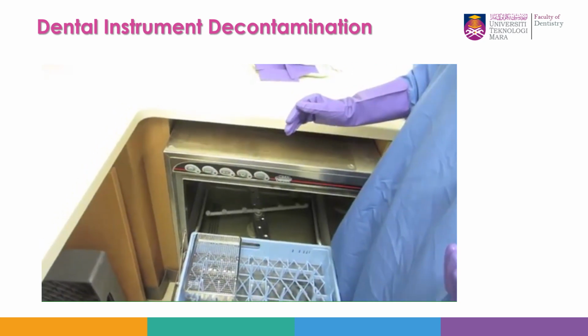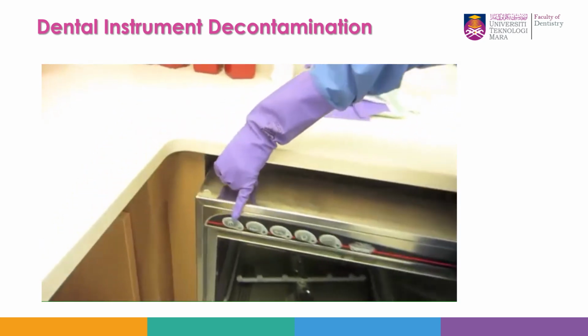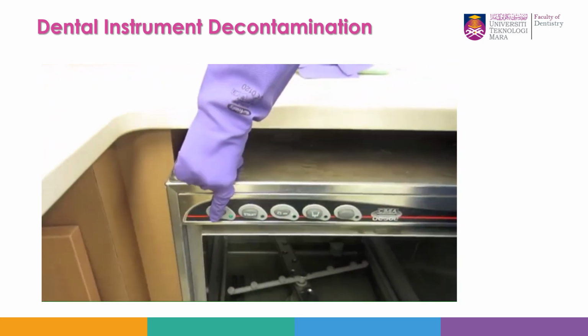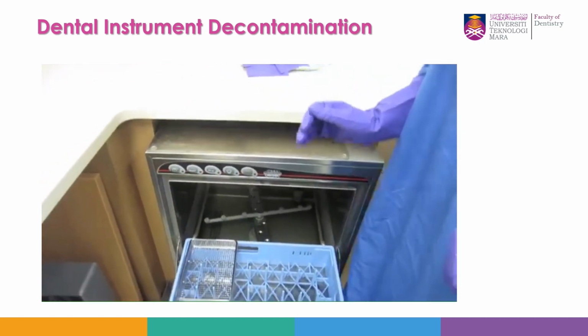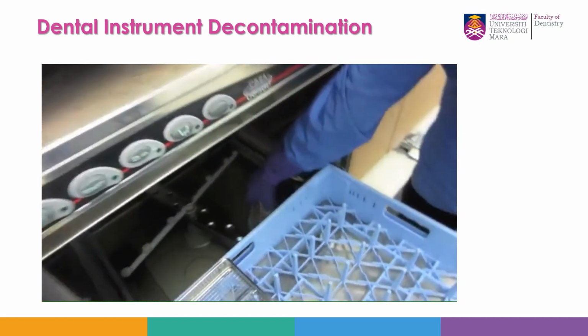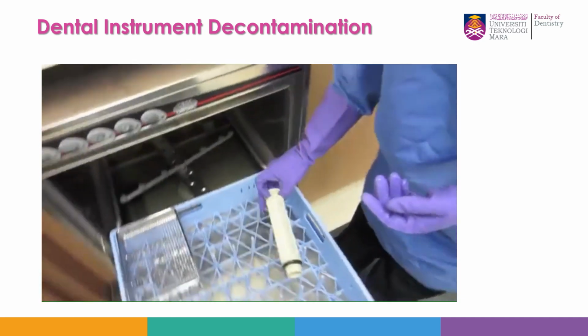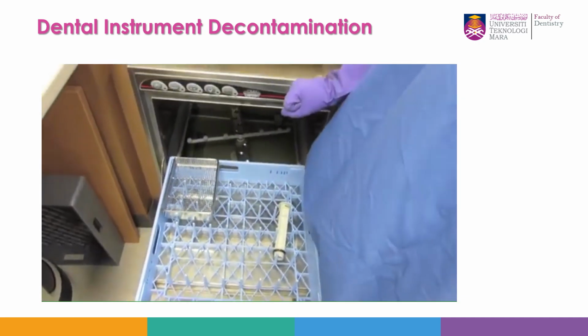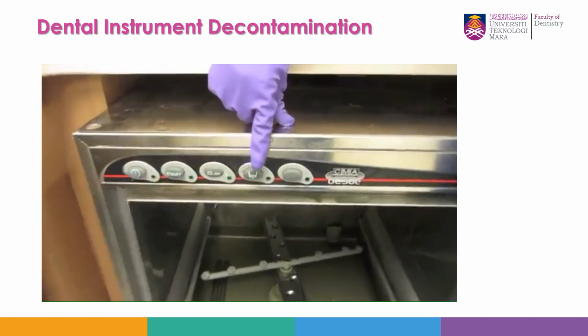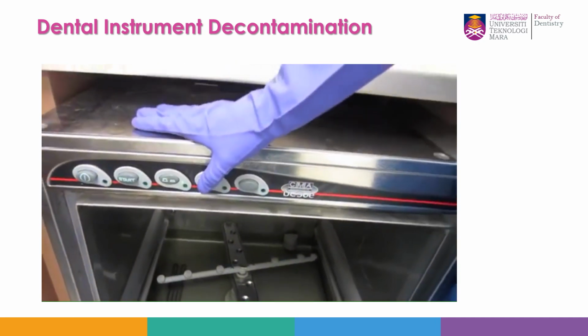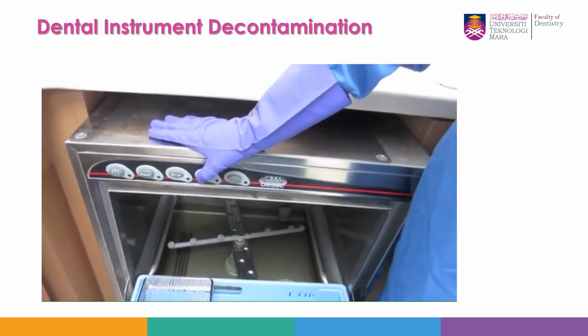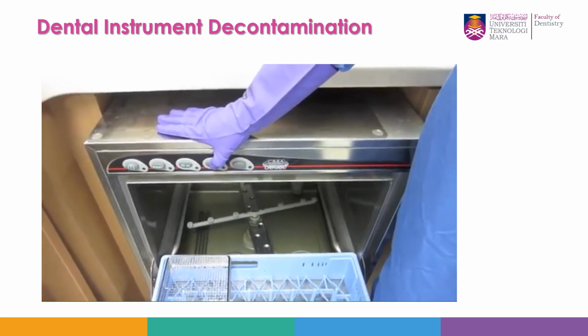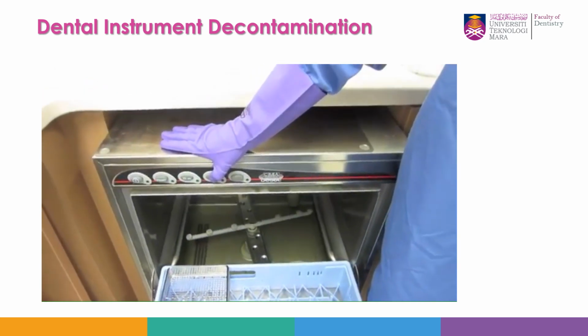At the end of the clinic station, turn off the on-off push button. Remove the overflow tube. Press the drain pump push button until all the water has completely emptied from the wash tank. A gargling sound will be heard when the water is completely drained.